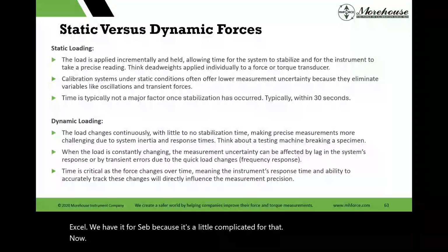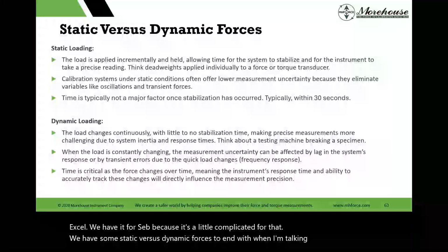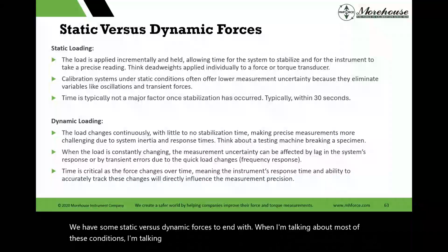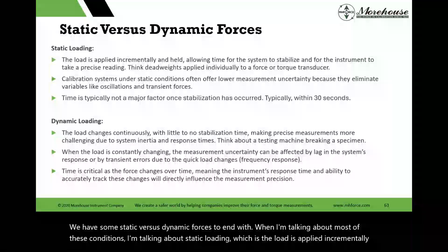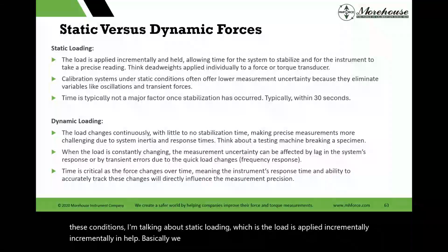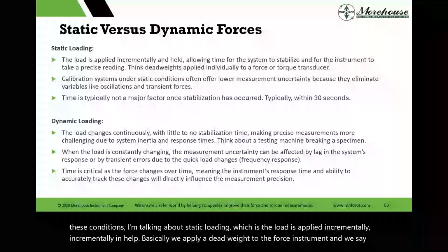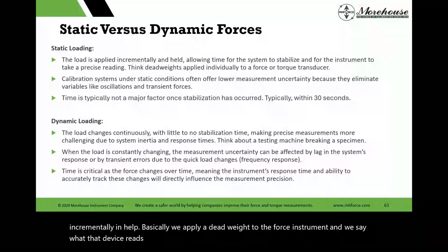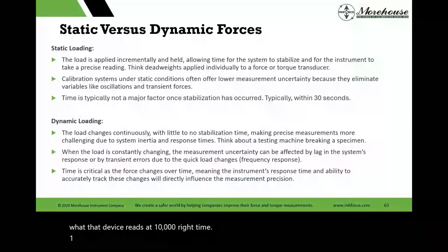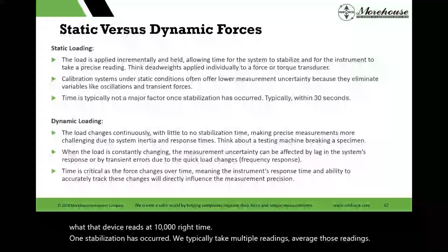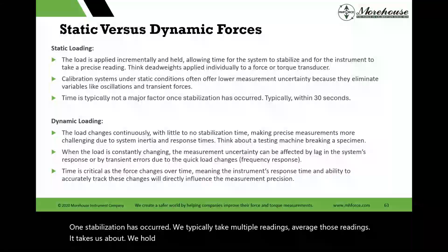Now, we have some static versus dynamic forces to end with. When I'm talking about most of these conditions, I'm talking about static loading, which is the load is applied incrementally and held. Basically, we apply a dead weight to the force instrument, and we say what that device reads at 10,000. Once stabilization has occurred, we typically take multiple readings and average those readings. We hold force for about 30 seconds.